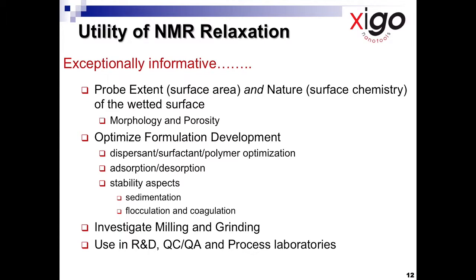We can also study stability aspects. If you have particles that are sedimenting, as they sediment, more liquid is exposed in the sensing zone, so the relaxation time will increase as particles sediment. This means you can study flocculation as well. There is a time mode in the ACORN area software that allows you to measure sedimentation rate.